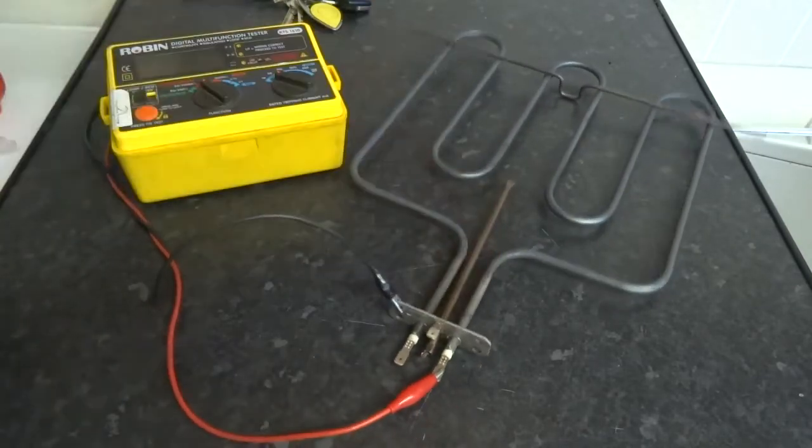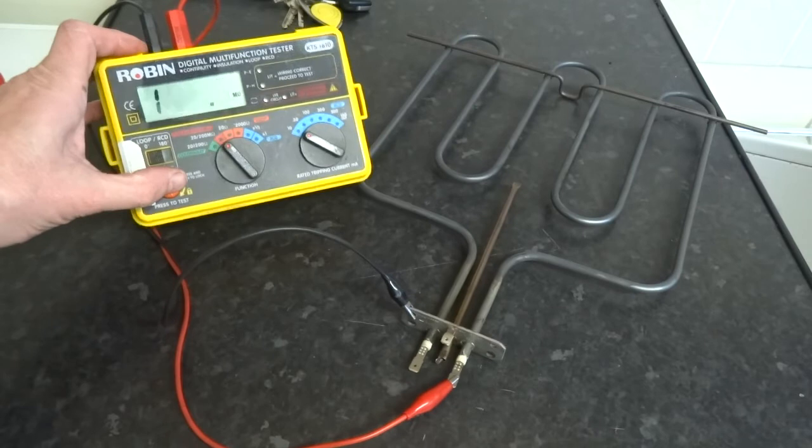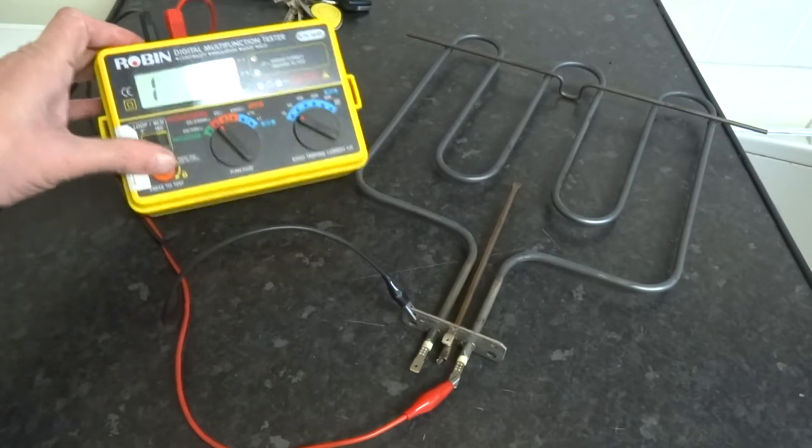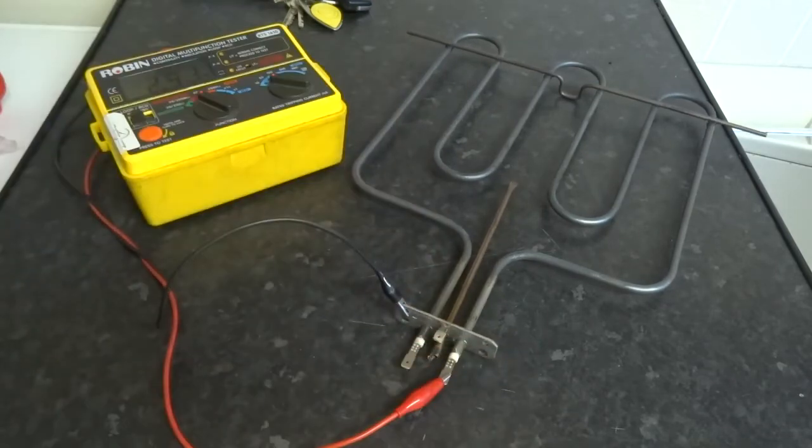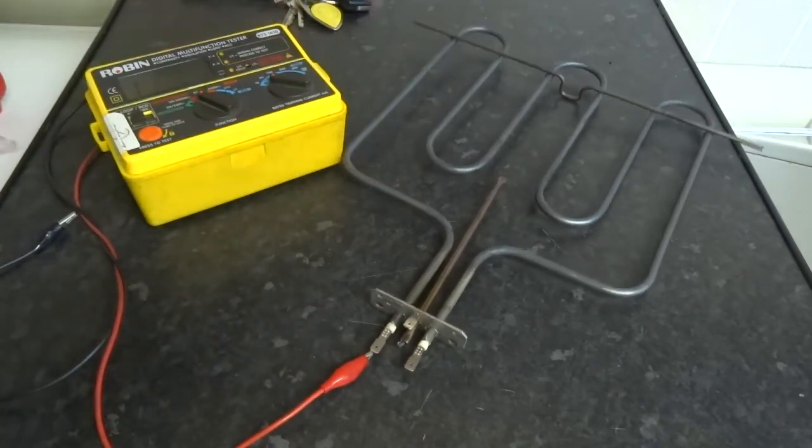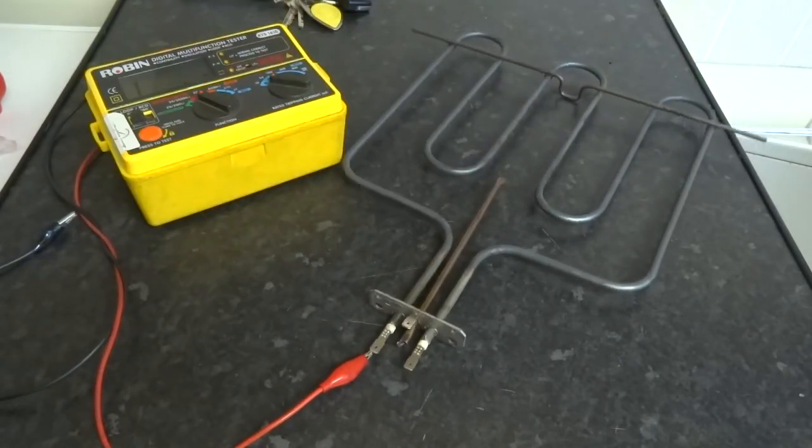Check the other side of the element. And it's gone right off the scale again. So you know it's good. So basically I know that this is electrically good and the insulation resistance is good.